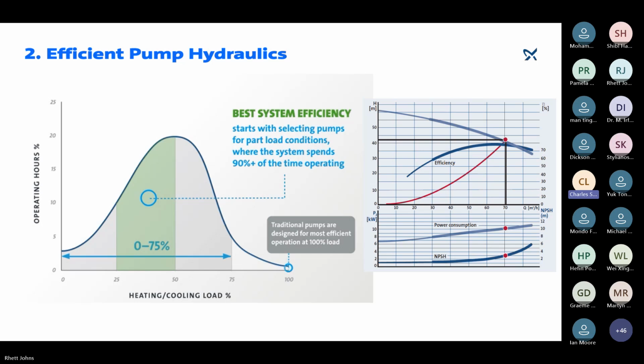So if that situation will only occur 5% of the time, then we want to make sure that our pump is selected so it's at its most efficient where we'll operate 90% of the time. And that's what you can see on this system curve on your screen. That's where our pump is going to spend most of its time operating, at normal conditions. So it's been designed to run at its most efficient. When it's running at its max conditions, it's not going to be running as efficiently as we want it to. And if you look at our curve on the right, you can see the relationship between flow and efficiency, and how it's at its most efficient at the duty set point, and efficiency drops off as flow is reduced. So again, we want to make sure that when we're selecting our pumps, we're selecting them with our most regular conditions in mind, and not the rated conditions, which is a common mistake that we know from pump suppliers when they're selecting pumps. Yeah.